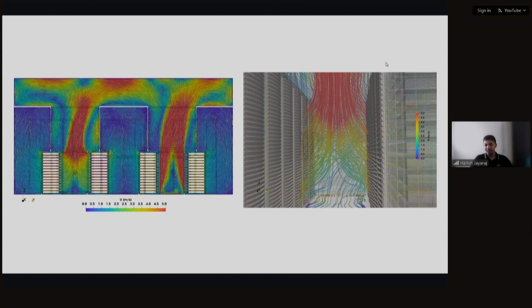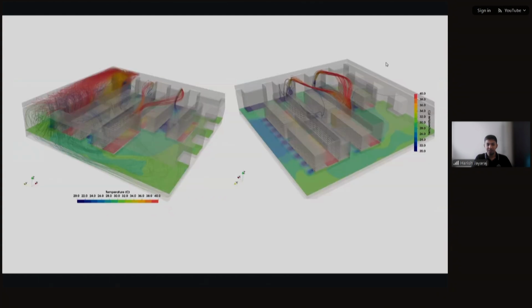On the right side we're looking at streamlines in the hot aisle, to see how close the racks should be placed to avoid heat flux from one rack affecting the other — the heat from one rack shouldn't heat up the other. So what should the distance be? This is more visual-based than data-based, and we have to figure out how many racks can safely be placed inside a room. This is another kind of visualization-based simulation.